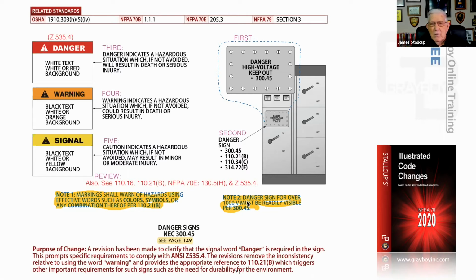These are systems over 1,000 volts. All cables here are now in Article 311. I like how they did this - they have cables in free air, and tables that take care of those cables. You have cables in raceway systems in free air, and cables in raceways inside the building or in the ground, all in order so you're not running through trying to find the right table for ampacity. Right at the front of Article 311, engineers can design the ampacity if they want on a high voltage cable run. We already gave you that table and section for 1,000 volts or less.